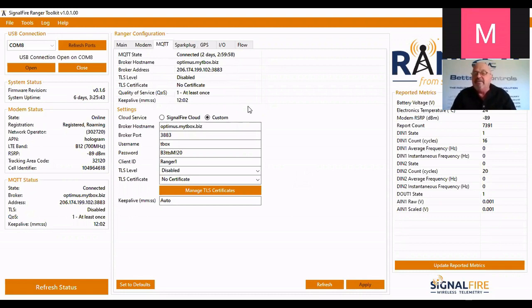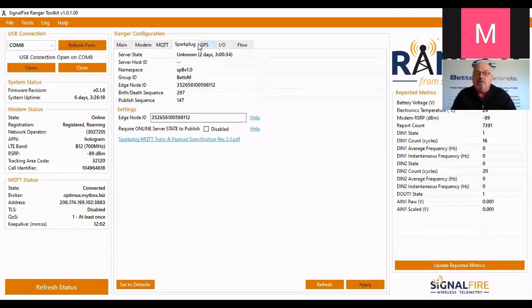This lets me configure the network device. I've got two choices: SignalFire Cloud, which takes it to their cloud service, or custom, which in this case I'm using because I've got a T-box RTU acting as a broker. So my broker name is Optimus mytbox.biz. It's got a port address, which I set, the username's T-box, it's got a password, and we gave it a name. Right now TLS is disabled because we were trying to avoid any issues with security. So that's basically how you set it up, and away she goes.